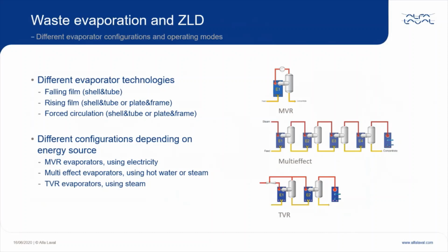When selecting your evaporator technology, it's also important to choose the optimal system based on availability and cost of different energy sources. The evaporation process, boiling of water, needs an energy source to drive the process, and that can be either a thermal energy source, such as steam or hot water, or it can be electricity, each offering different advantages. In the mechanical vapor recompression or MVR system, using only electricity to drive the evaporation process, the water vapor that has boiled off from the product in the evaporator is compressed in a mechanical compressor or fan and can then be used as the heating media for the evaporating process.